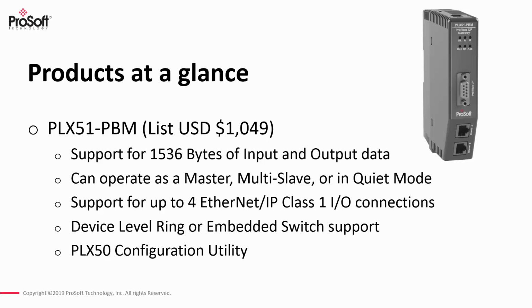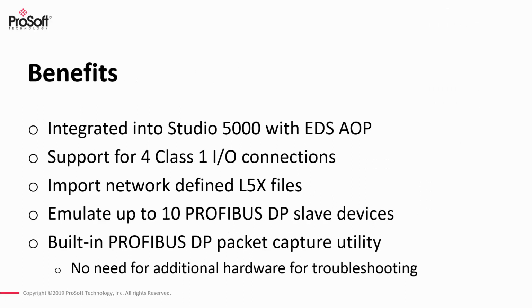So we also, like I mentioned, are supporting device level ring, and so that gives you your redundant Ethernet connection. And in networks where you don't necessarily need the redundant network connection, you can use it as an embedded switch. So the module can operate as a two-port switch, and so that helps to eliminate potential additional switches in a cabinet, or allows you to daisy chain other devices, other than Ethernet IP devices, off of the module. And then this does take advantage of our PLX50 configuration utility, which is one of our newer utilities, and we've got some good features in there for getting these integrated into your system quicker. So I'll talk about that in a little bit as well.